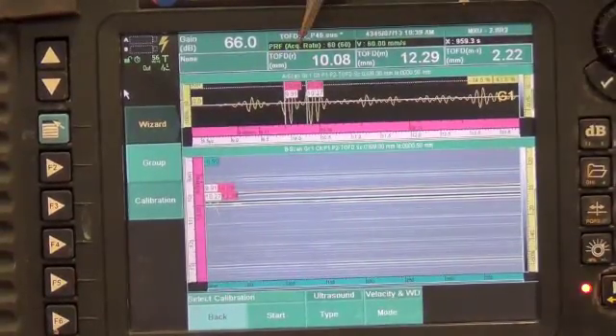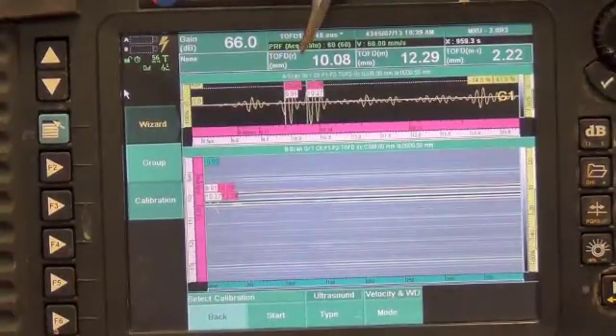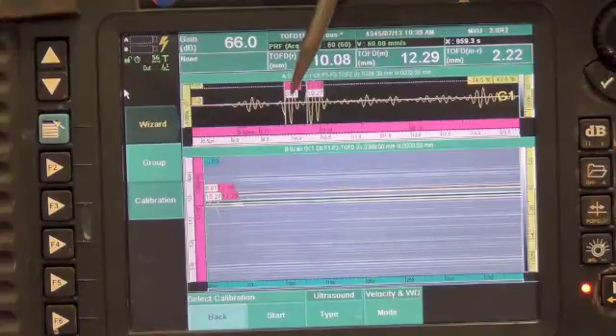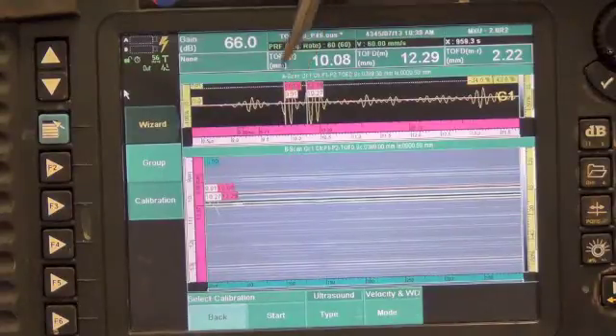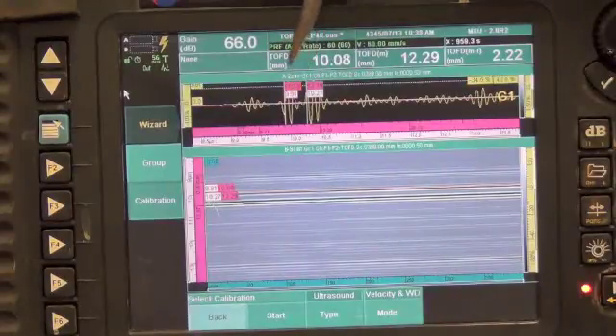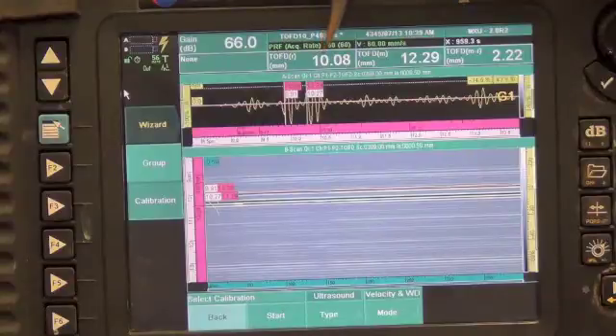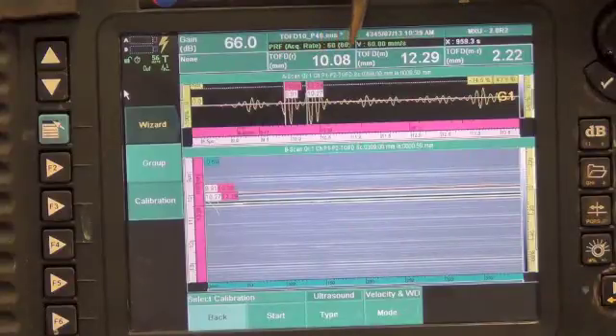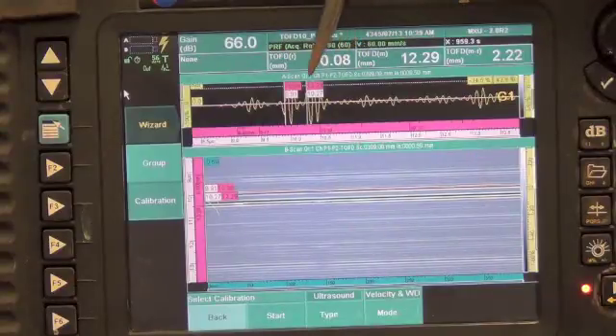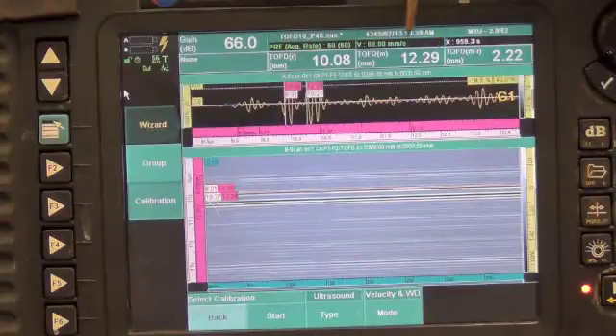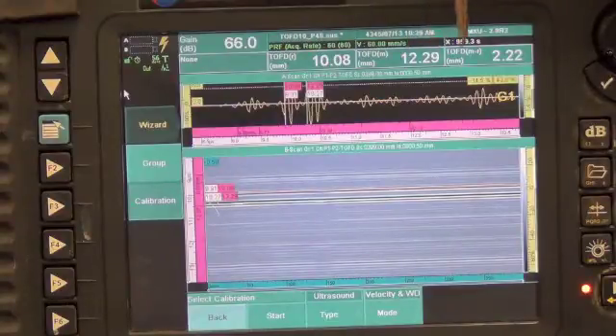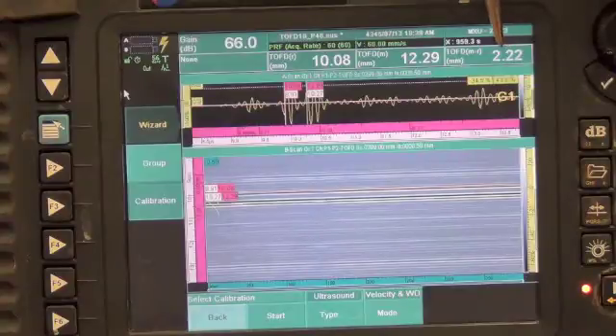Now to verify the calibration, this is the top of the second hole and it is measuring as 10.08mm. The bottom of the hole is at 12.29mm, so the size of the hole is being measured as 2.22mm.